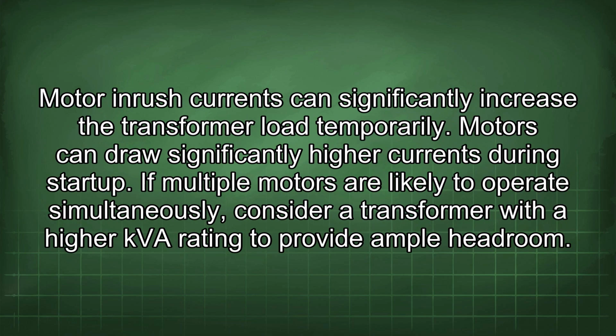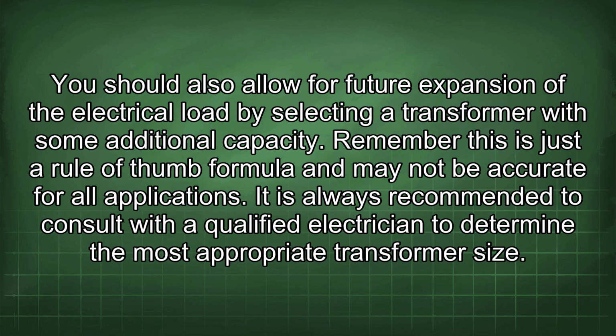Motor inrush currents can significantly increase the transformer load temporarily. Motors can draw significantly higher currents during startup. If multiple motors are likely to operate simultaneously, consider a transformer with a higher kVA rating to provide ample headroom. You should also allow for future expansion of the electrical load by selecting a transformer with some additional capacity. Remember, this is just a rule of thumb formula and may not be accurate for all applications. It is always recommended to consult with a qualified electrician to determine the most appropriate transformer size.